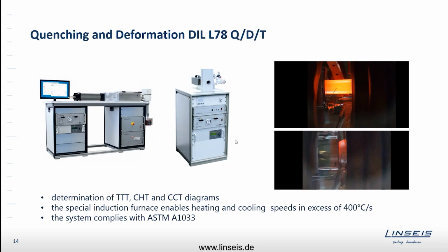The next instrument of our special instrument series would be the quenching dilatometer. As said, it's an inductive system. It is available as heating and cooling only, or with an actor for deformation studies. Here, the setup is a little different. So it's again a pushrod system. You have quartz pushrods that are touching the sample. You can also have ceramic pushrods for higher temperatures. And the sample is clamped between two pieces of rod. And then there is a magnetic coil with a magnetic field generator surrounding the sample.